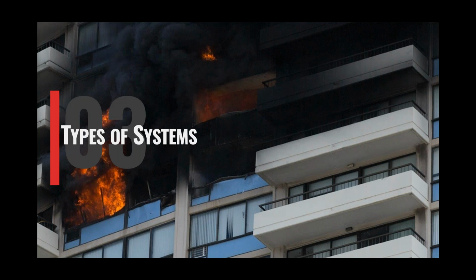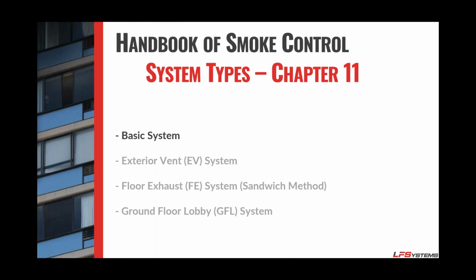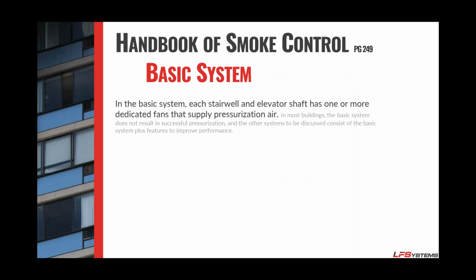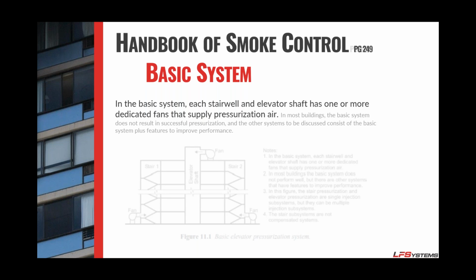What are the 4 types of systems listed in Chapter 11? One is a basic system, then the exterior vent system, a floor exhaust, which sometimes people call the sandwich method, and finally a ground floor lobby system. So we'll start with the basic system. As you would expect, the basic system is pretty basic. You get a fan for each stairwell and a fan for the elevator shaft, you turn it on, and you get what you get. It's a fixed speed system. There's no control, there's no variance. You just get whatever that system was balanced to during commissioning.